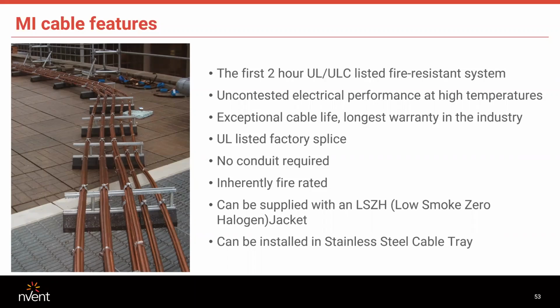So, of course, what you support and bundle the cable with has to have a fire rating for 2 hours. So we recommend, we require rather, steel supports. Unistrut works great. And steel clips. Stainless steel hose clamps are fine. We have our own steel clips you can use, but that's what we require for fire rated applications. Now, by chance, if you happen to be using MI cable for a non-fire rated application, then you could support it on whatever you want because it's not being used for a fire rated application. But when it's used for a fire rated application, you do need a 2 hour fire rated support system.